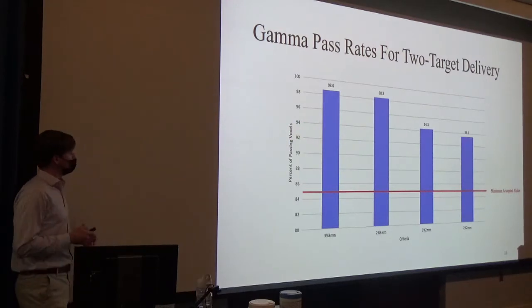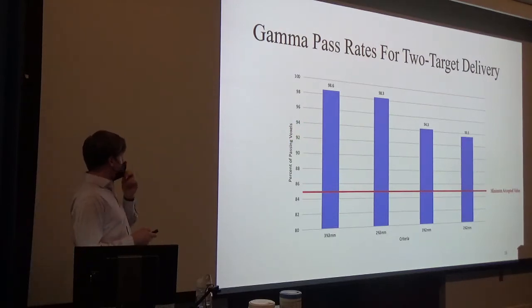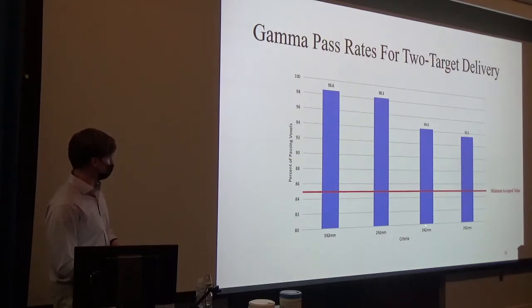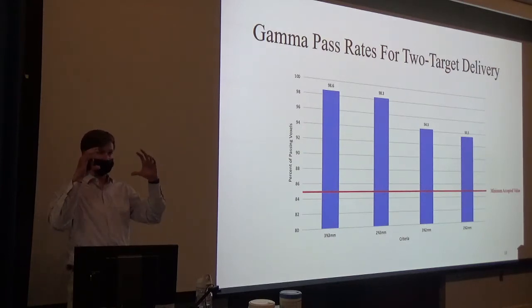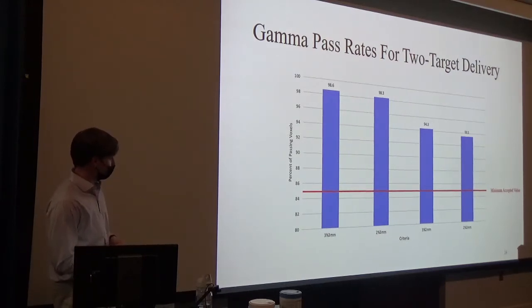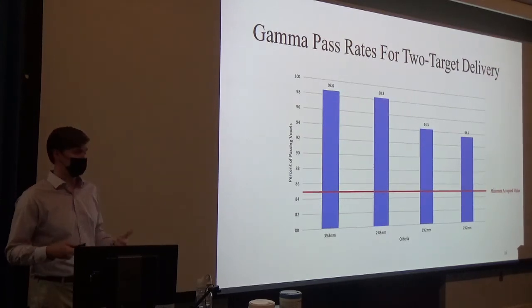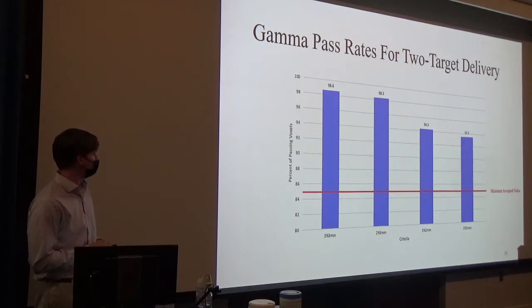The results of this two-target delivery were extremely good. On the x-axis we have decreasing criteria — that ellipsoid getting smaller and smaller. Even down to our most strict criteria of 2% and 2mm, we're well above the minimally accepted value for clinical and hospital applications at the current time, which is really promising.